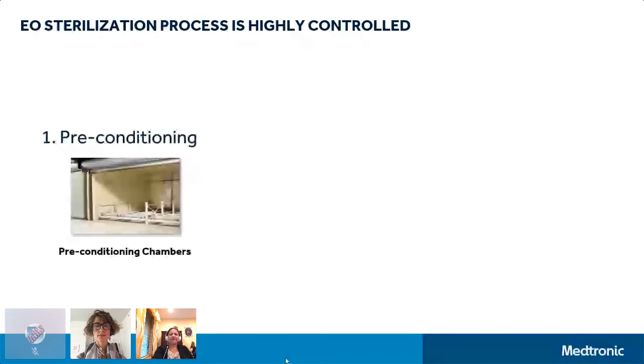And then this slide shows a snapshot of the chamber sizes that are used for different stages of the EO processing: the preconditioning, the actual processing chambers, and the aeration. And as you can see, we can load more than 30 pallets of fully assembled and packaged devices here.